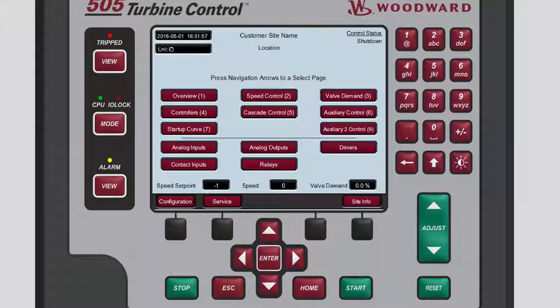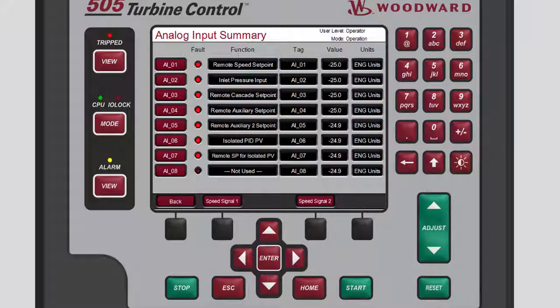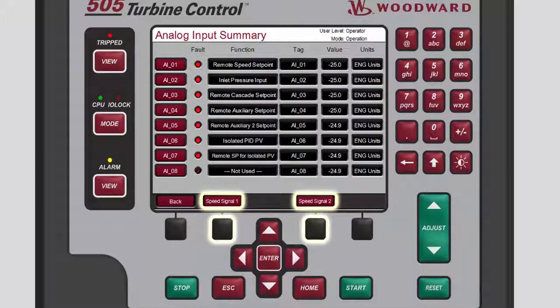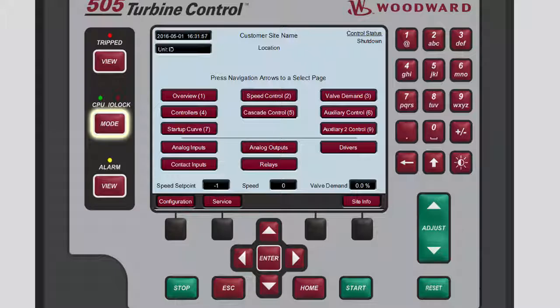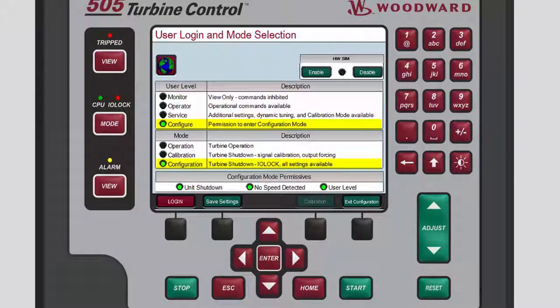Let's examine one of the input screens. Select Analog Inputs to open the Analog Input Summary screen. On this screen, you can see what values are available for each channel. You can also access the two speed input signals from this screen by pressing the black function key below the desired speed signal number. To set up the input-output channels, place the unit into Configuration Mode and then select and change each channel for the different input-output types. Please note that the Changing User Levels tutorial explains how to change to the Configure User Level, which is required before placing the unit into Configuration Mode.